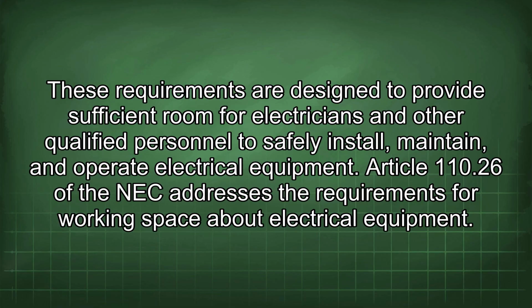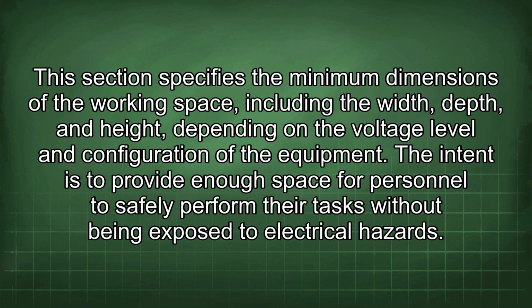Article 110.26 of the NEC addresses the requirements for working space about electrical equipment. This section specifies the minimum dimensions of the working space, including the width, depth, and height, depending on the voltage level and configuration of the equipment. The intent is to provide enough space for personnel to safely perform their tasks without being exposed to electrical hazards.